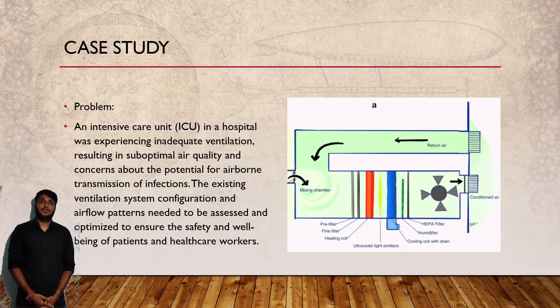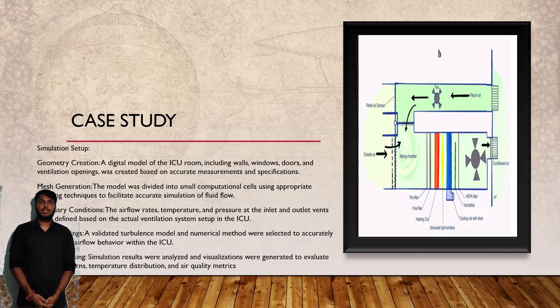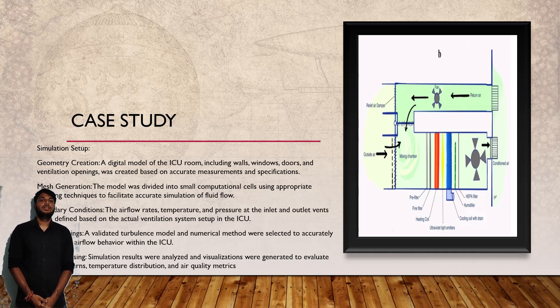Now let's talk about a case study. The initial problem was the presence of inadequate ventilation in the ICU, leading to suboptimal air quality and concerns about infection control. This prompted the need for a thorough assessment and optimization of the ventilation system. The first step in the CFD analysis was to create a digital model of the ICU room incorporating accurate measurements and specifications. This 3D model includes walls, windows, doors and ventilation openings to replicate the actual environment. The model was then divided into small computational cells using appropriate meshing techniques, allowing for accurate simulation of fluid flow dynamics and capturing of detailed airflow patterns.